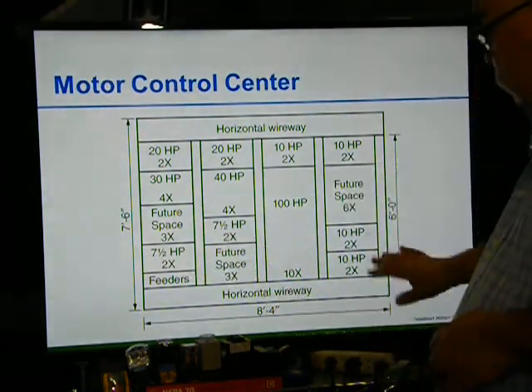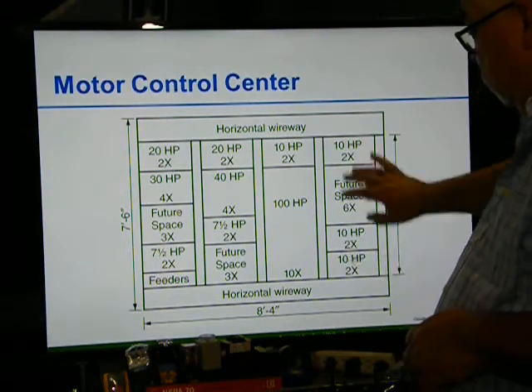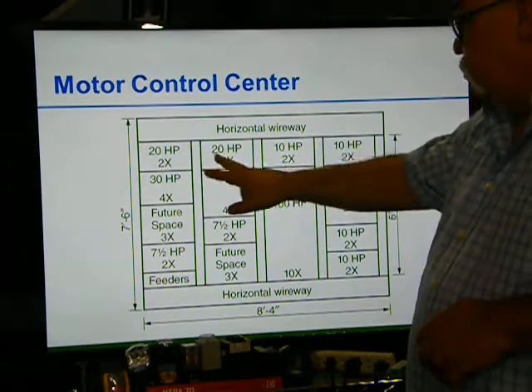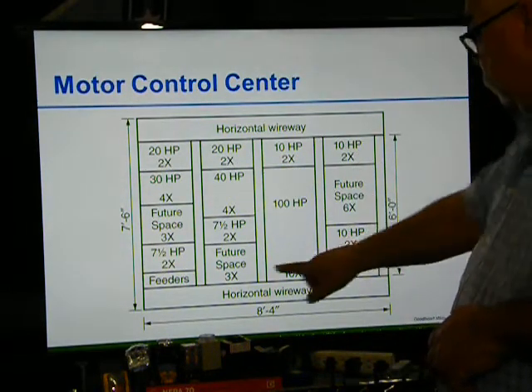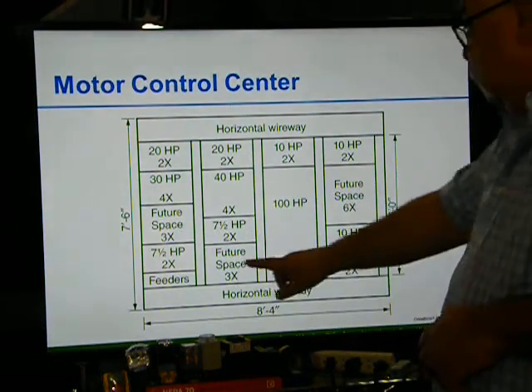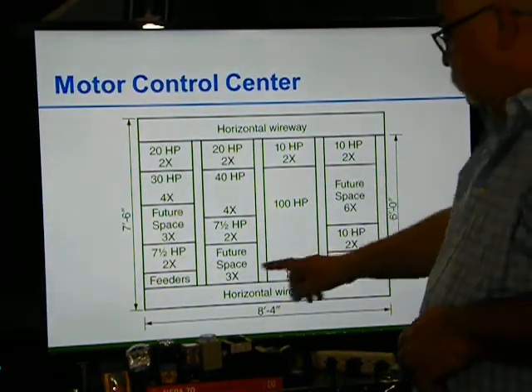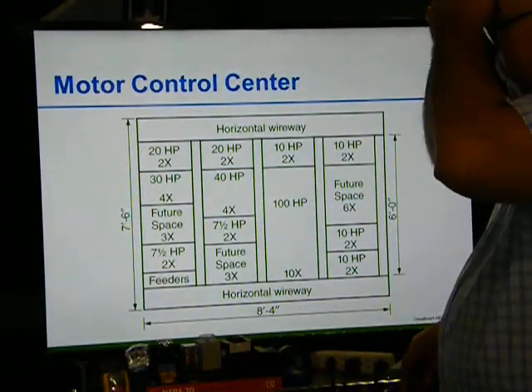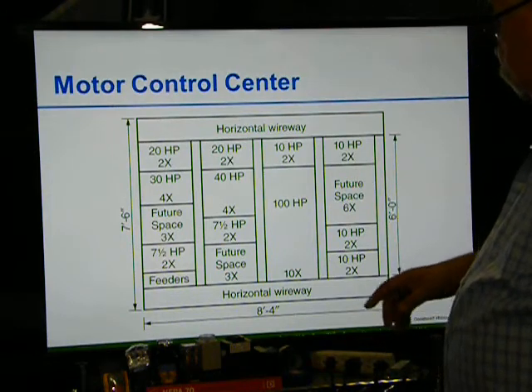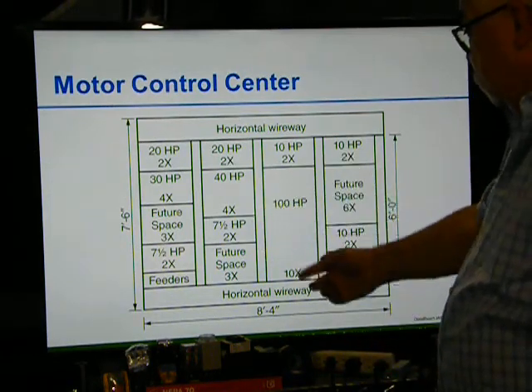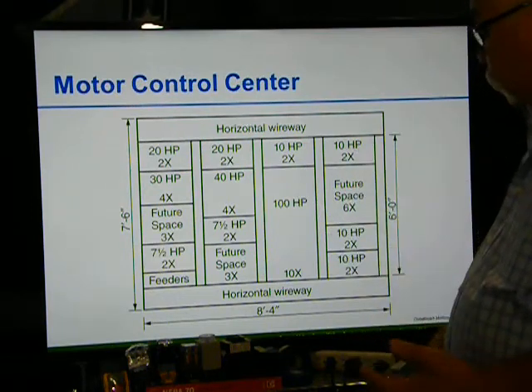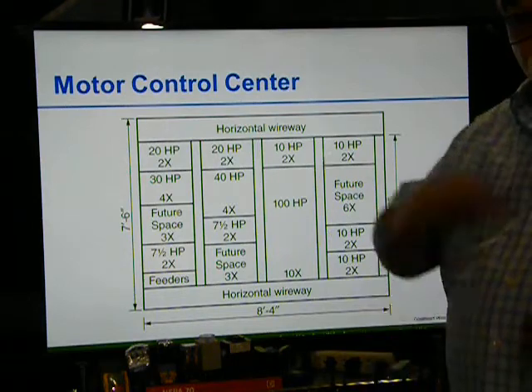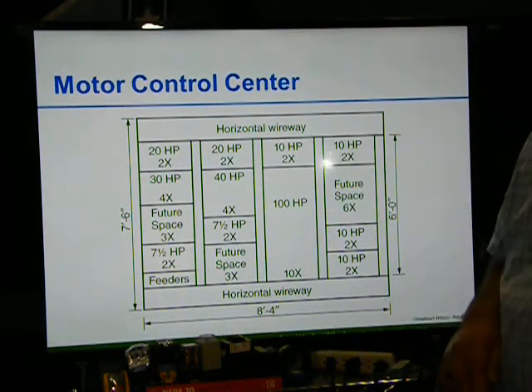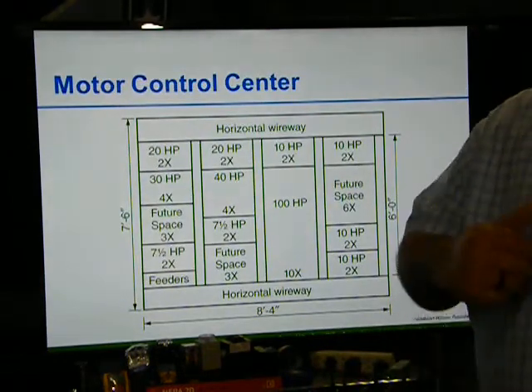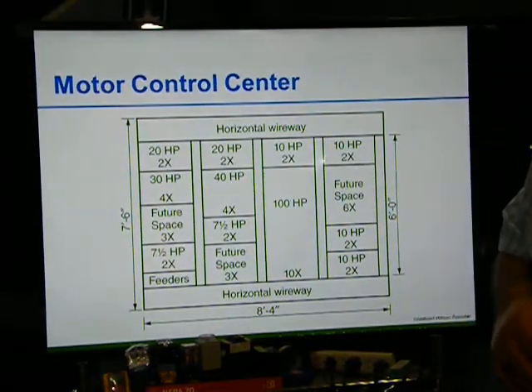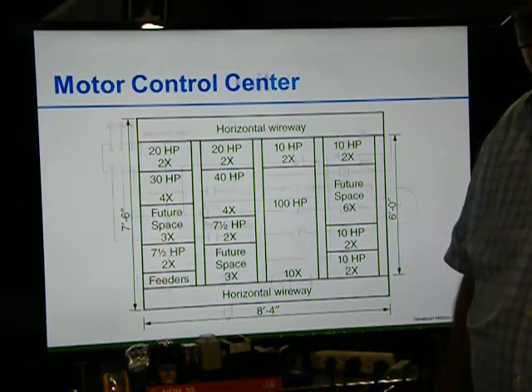Okay, so this is your MCC, so you can control. You can see they got 100 horsepower, 20, 20, 10, 10, future, future, future. On the future they got 3 different sizes. Where it says 3 times, 4 times, 2 times, I guess must be the size. Here's 10 times bigger. But it allows you to get so much. This can be divided in case you have to. They do make dividers, and you can divide some of these into 2. Each has 1 door. It's a matter of changing the door, changing the inside, and you can make your connections. So motor control center, I'm trying to find a picture in a bit.